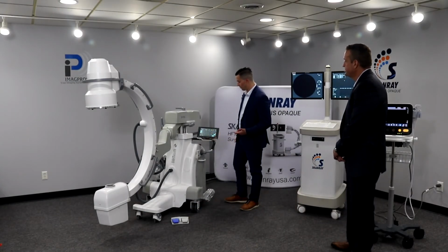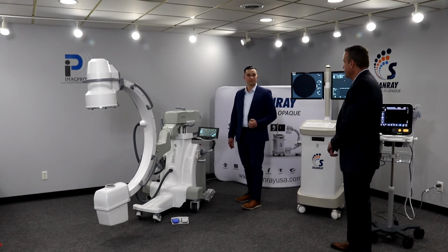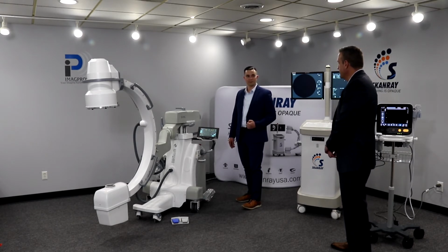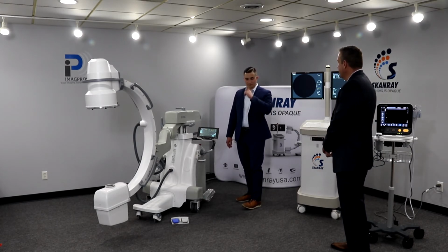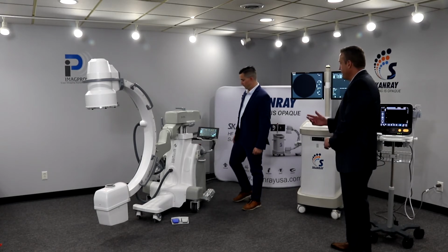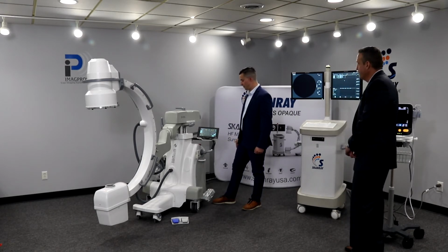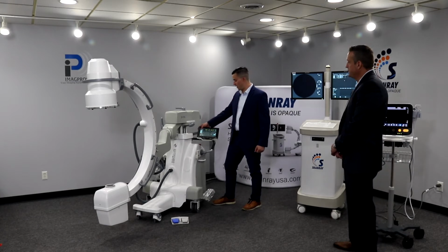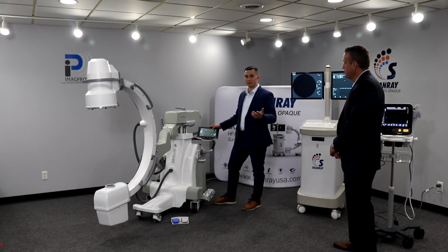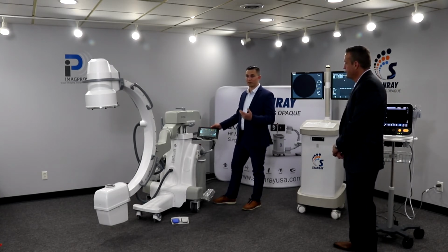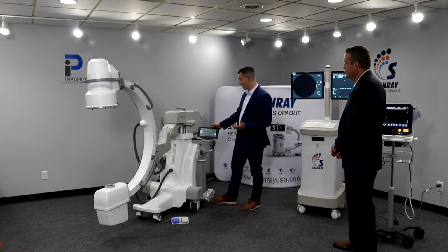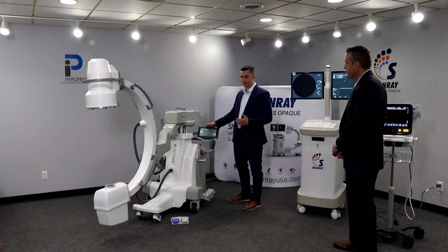Even if this whole screen were to get cracked or destroyed, you would be able to continue the procedure with your manual buttons. Excellent. Aaron, can you talk a little bit about the auto technique and when we compared it to some of the competitor systems? It kind of gets back into radiation exposure. Absolutely. So our auto technique ties into what we discussed earlier with the high frequency generator and the X-ray tube. We're able to take images at a much lower kV and mA compared to other systems.